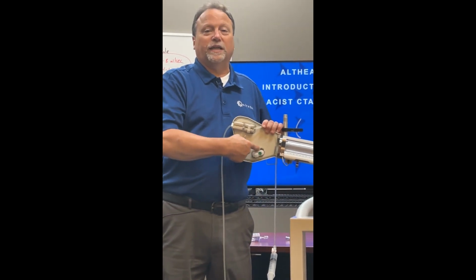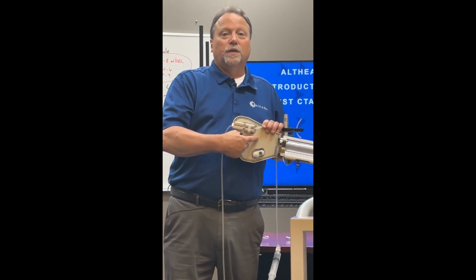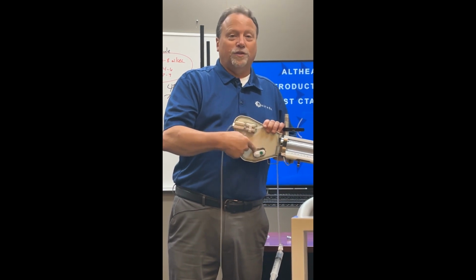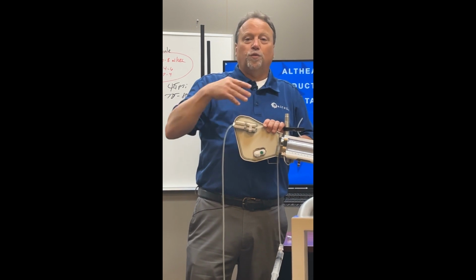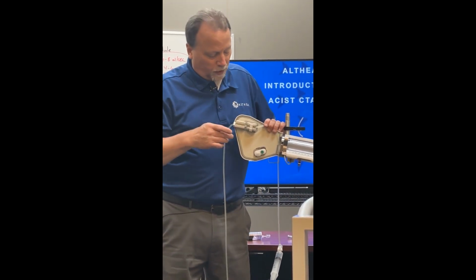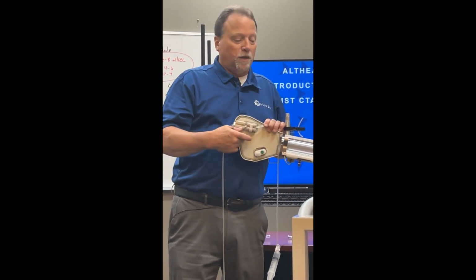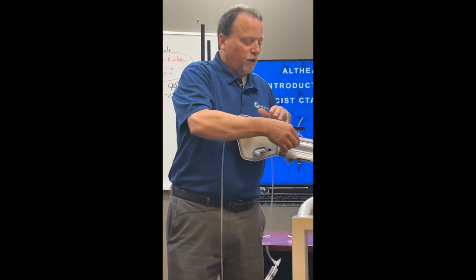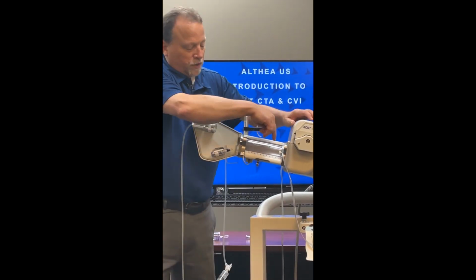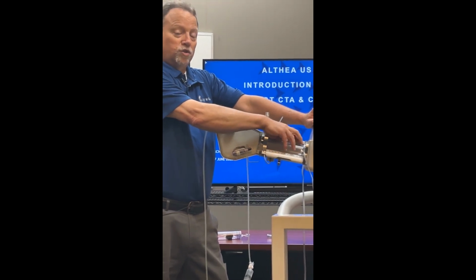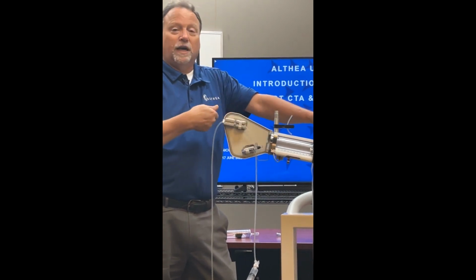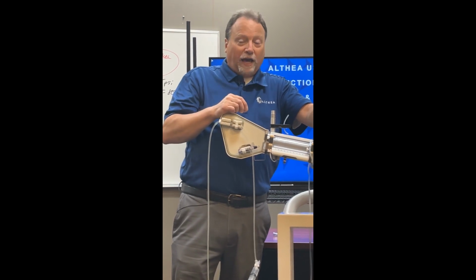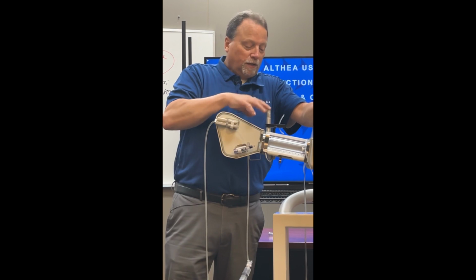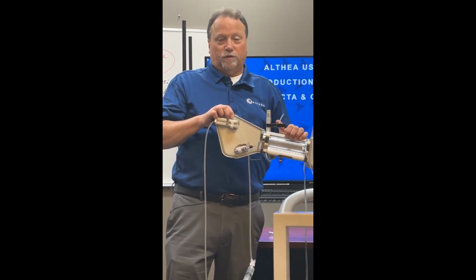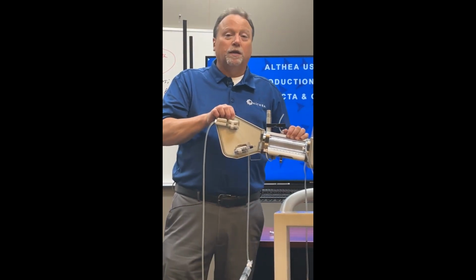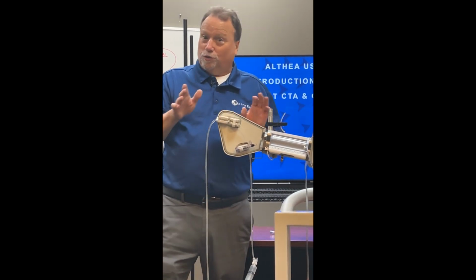This is a dangerous situation because it can actually spark and arc and burn up the rest of the injector. Without proper cleaning and maintenance, this will happen. Now, here at Althea, we can replace these significantly cheaper than what Acist charges, but it's still an expensive repair. So maintenance around the light assembly is very important. This is one area that is a problem, and also inside the chamber. There is a drain hole inside the chamber, and it gets clogged with contrast. So any fluid contrast will just sit in there and seep inside the light, and we've actually had instances where there's arcing. You can actually see the arcing going on when the lights are turned low. Again, dangerous situation. Contrast will eat right through this. If you see any of this, then these should be replaced immediately, because you never want arcing and sparking during a procedure, do we? Okay?